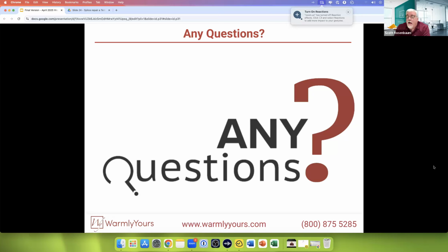What's the red flag to me here is, when we read stuff like this, there's usually a red herring or a red flag that pops up. And the red herring in that statement is that the kits are connected near my breaker panel. Well, when you're connected near a breaker panel, that usually tells me that there's some wiring that the electrician supplied between the breaker panel area and the floor in that room.